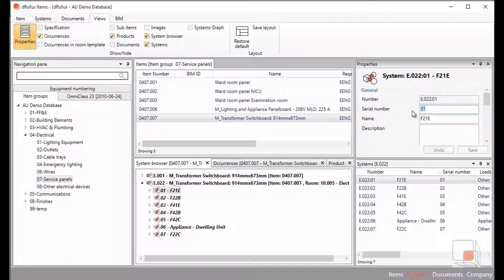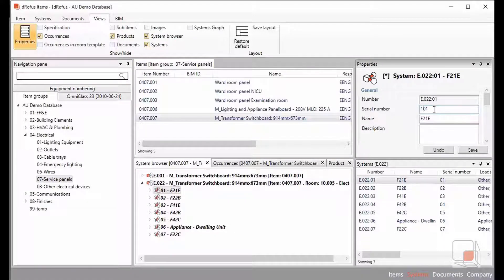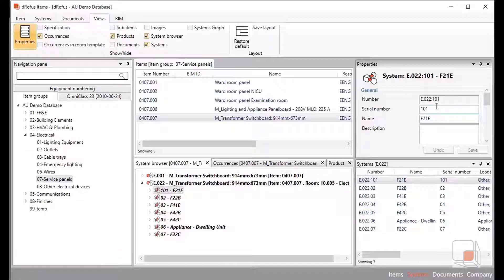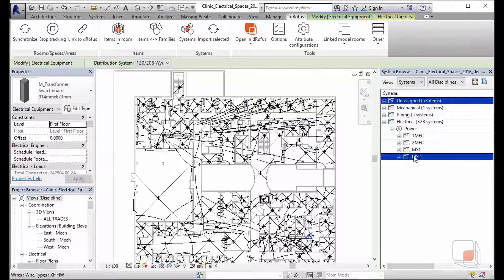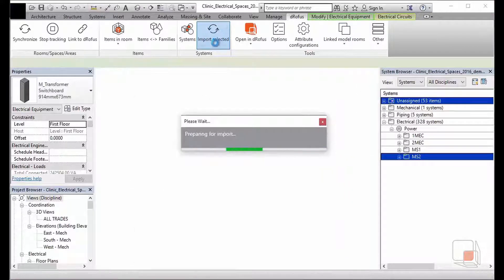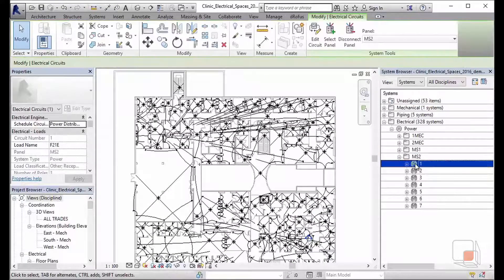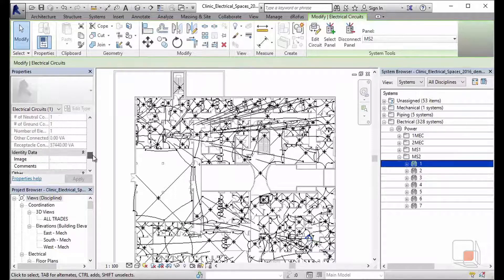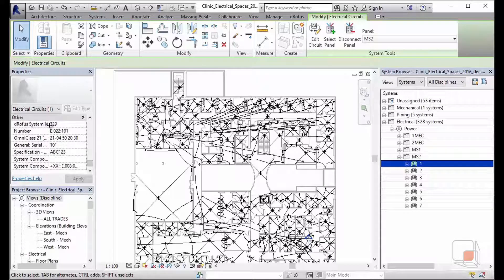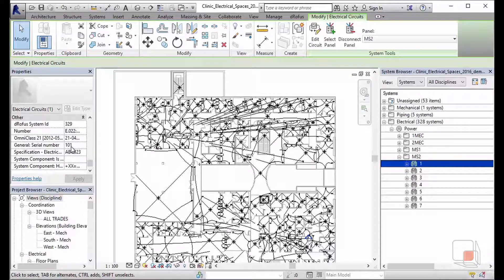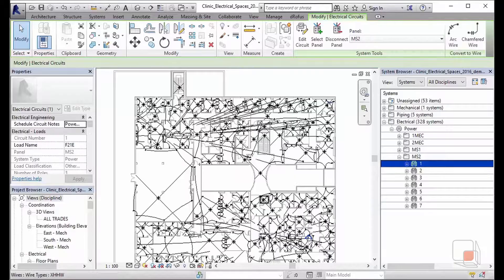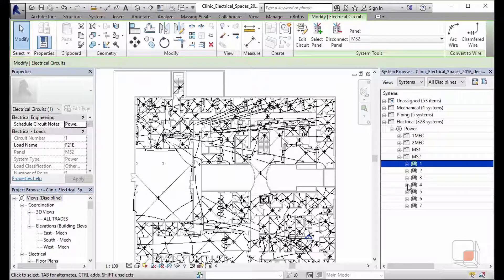For example, if I take the serial number that was 01 that pulled from Revit, I can change this to 101 and simply synchronize that effort with my dRofus information to my Revit panel information. Doing the same import selected icon, this time will now synchronize those components. Now that those components have been synchronized, if I drill into that circuit, I can now see that the circuit has changed from 01 to 101. So I can start to manage some of these occurrence parameters in my Revit environment from my dRofus component environment. This offers some additional flexibility in the design process.